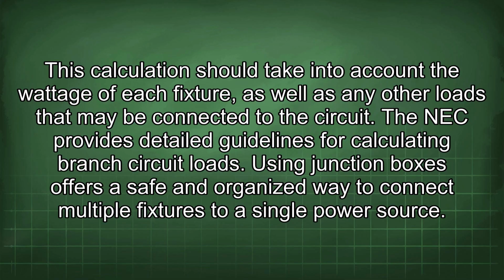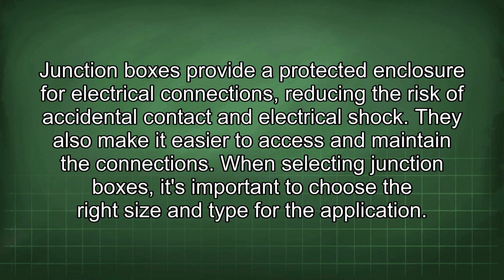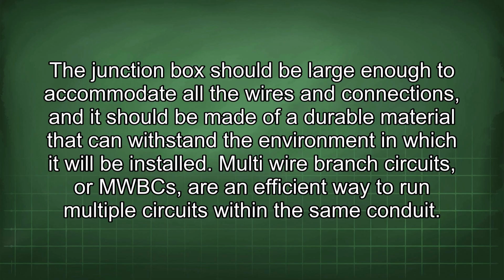Using junction boxes offers a safe and organized way to connect multiple fixtures to a single power source. Junction boxes provide a protected enclosure for electrical connections, reducing the risk of accidental contact and electrical shock. They also make it easier to access and maintain the connections. When selecting junction boxes, it's important to choose the right size and type for the application. The junction box should be large enough to accommodate all the wires and connections, and it should be made of a durable material that can withstand the environment in which it will be installed.